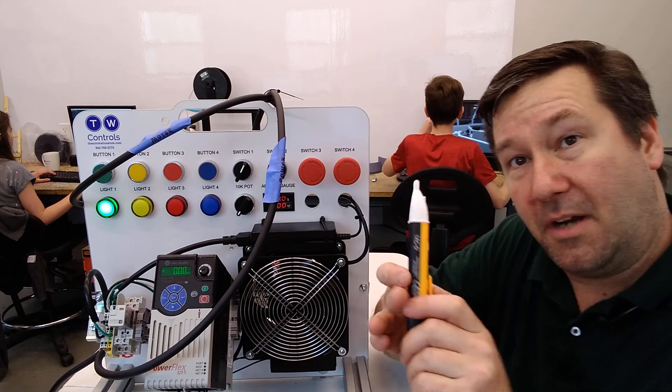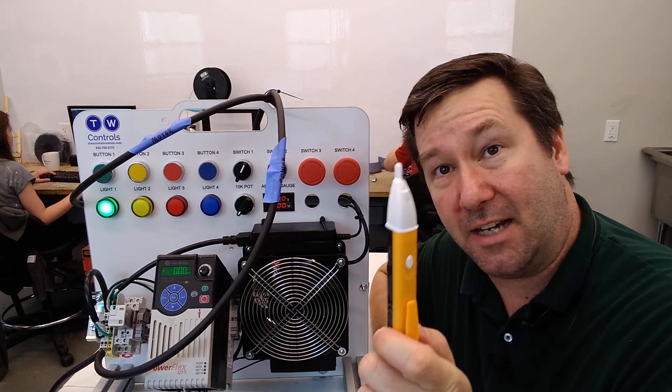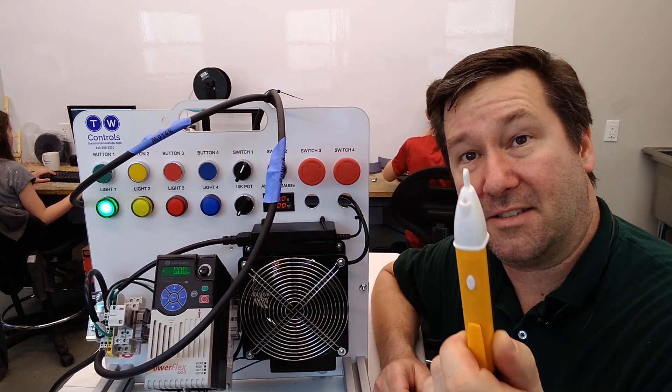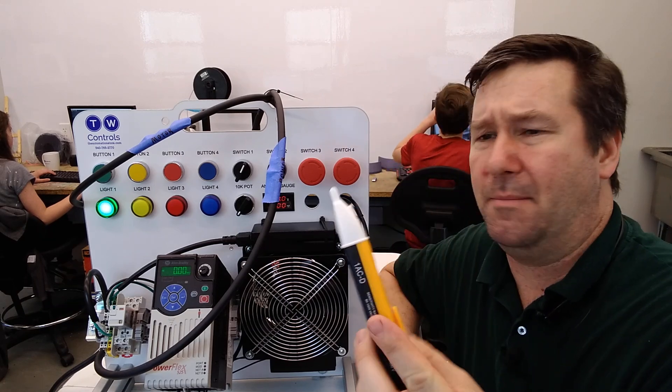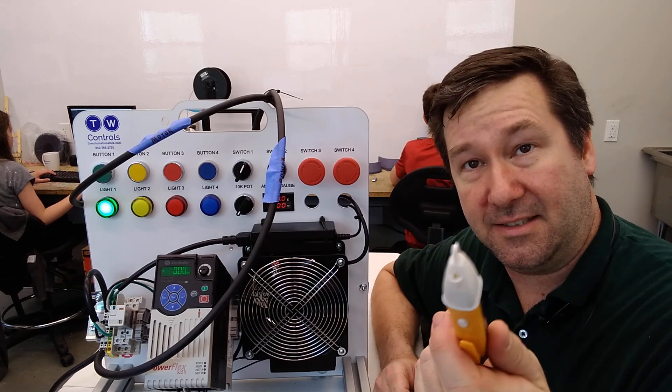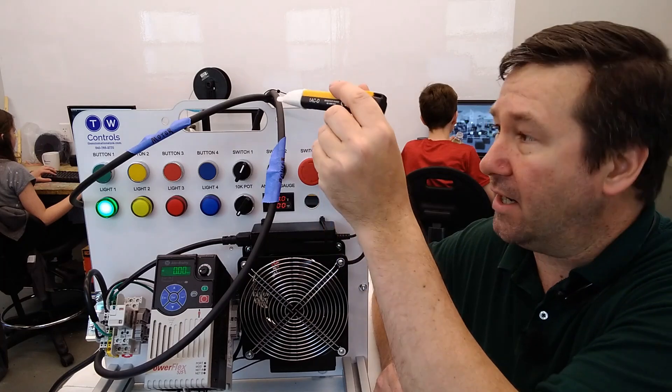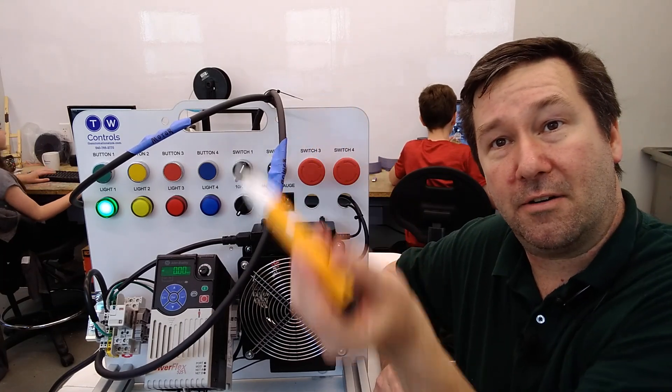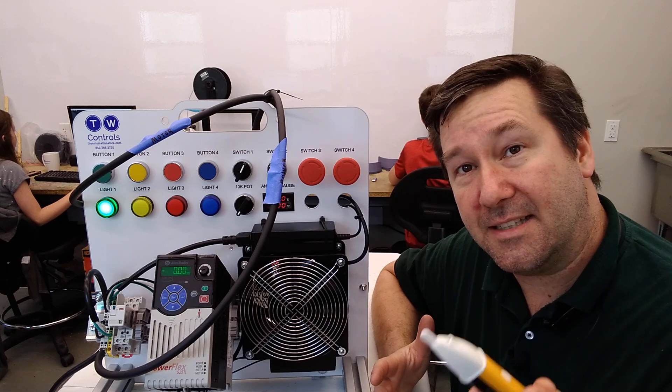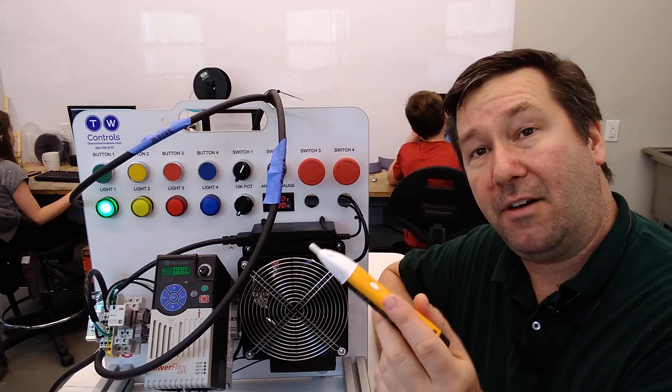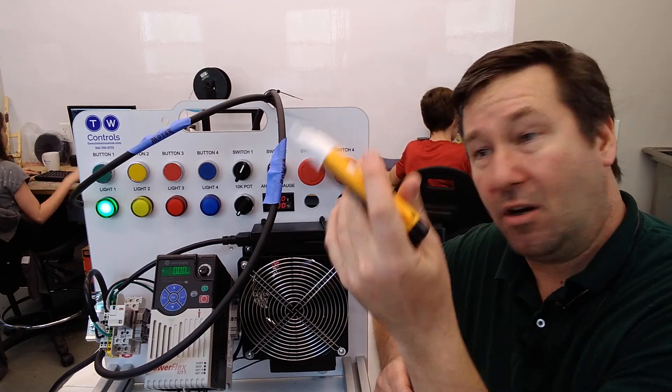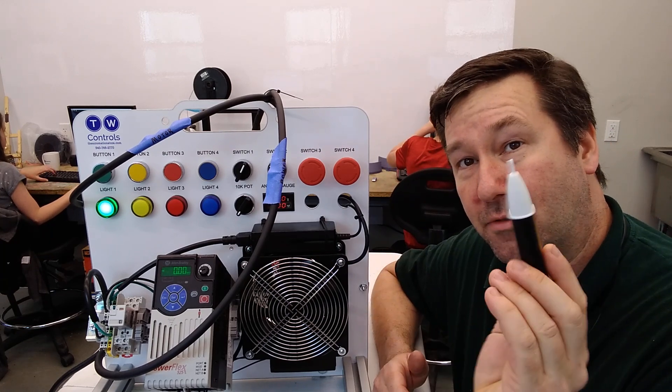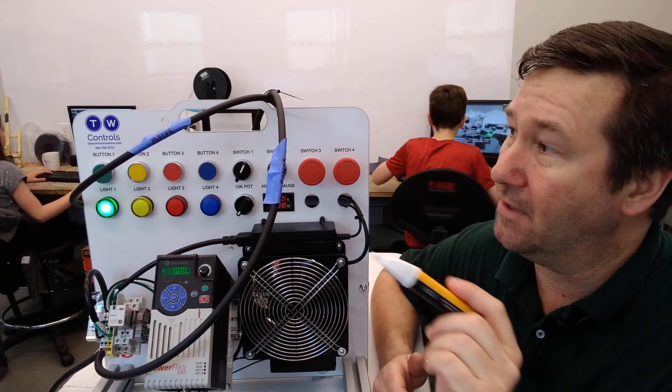Now first, I'm not bashing the non-contact voltage sensor. These are super important, especially in lockout tagout procedures. And yeah, we probably ought to do some videos on that because these could save your life. But if you run a non-contact voltage sensor across a wire, you'll know whether it has AC power without actually piercing the wire or exposing any of the conductors. Now this only works with AC, and we'll talk about that near the end of the video.